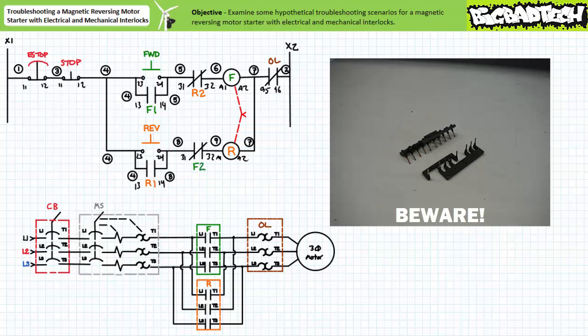Additionally, I've observed undisciplined lab groups fail to tighten all the terminals of the pre-configured reversing wire kit. Although physically inserted into the correct terminals, no electrical contact is made, and the system will not function as intended.